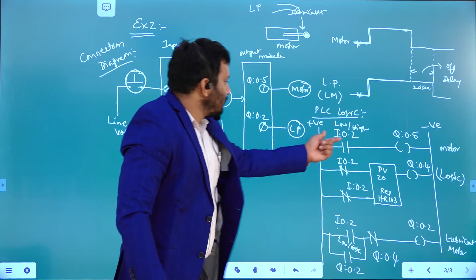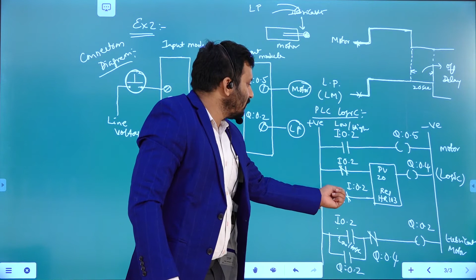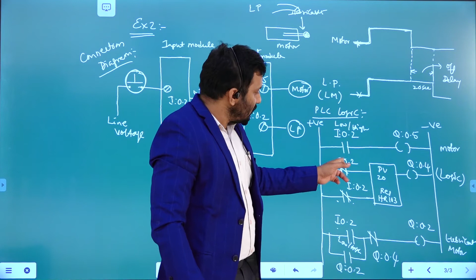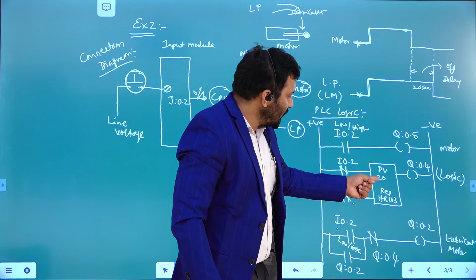After 20 seconds, this is low, so what will happen? If it is on, both are in this state, and this particular timer is going to work. If it is high, it's on only, but this timer is not going to be reset or run. Whenever you switch this off by opening this switch and it is low, this is also reset and it starts running. These two inputs are in the normally closed condition, so it is reset and keeps on incrementing until 20 seconds is reached.